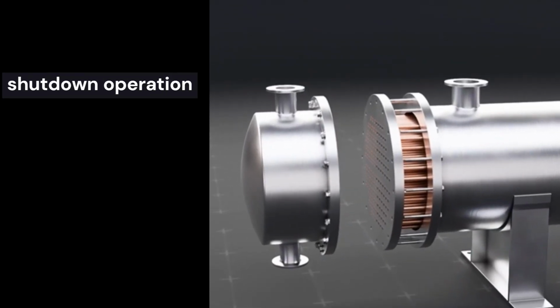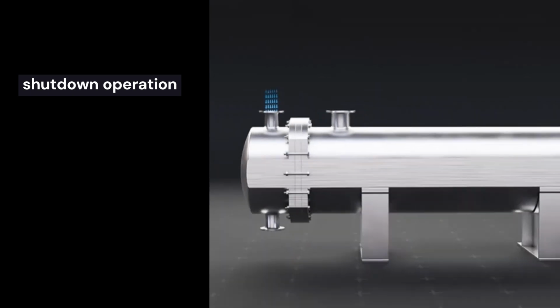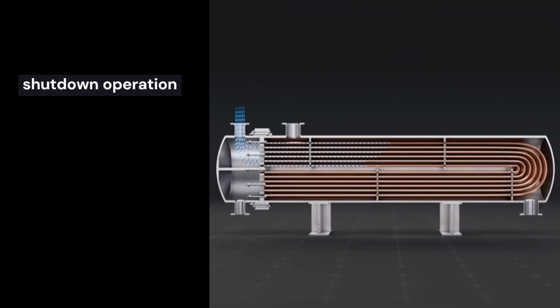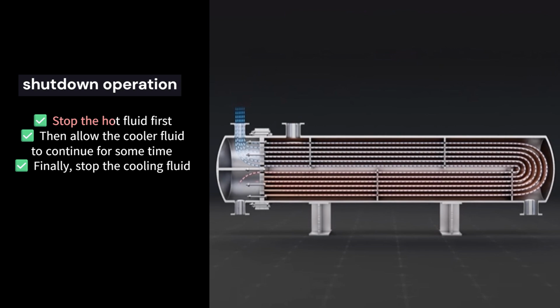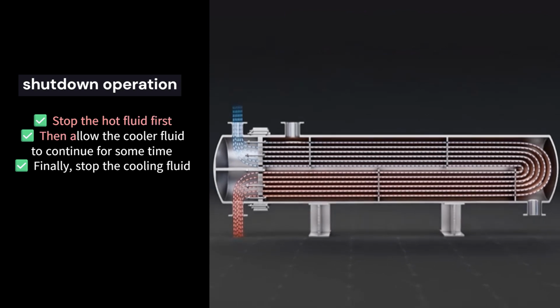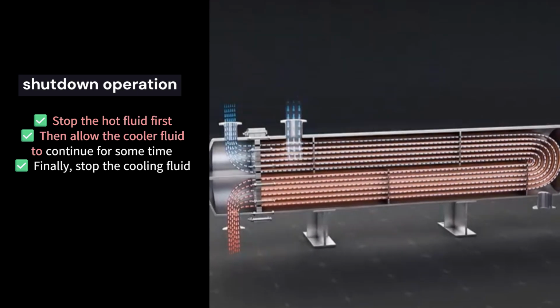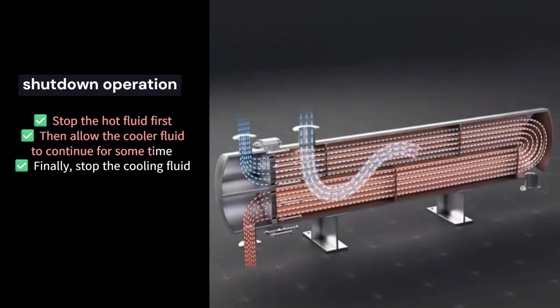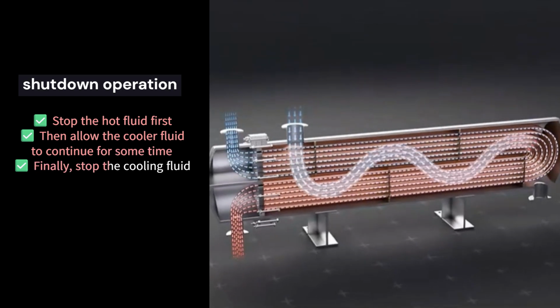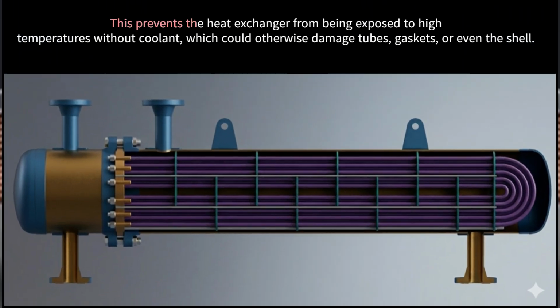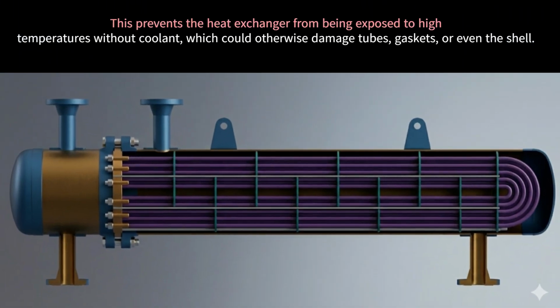Now let's move to shutdown. During shutdown, the sequence is exactly the opposite. Stop the hot fluid first, then allow the cooler fluid to continue for some time. Finally, stop the cooling fluid. This prevents the heat exchanger from being exposed to high temperatures without coolant, which could otherwise damage tubes, gaskets, or even the shell.